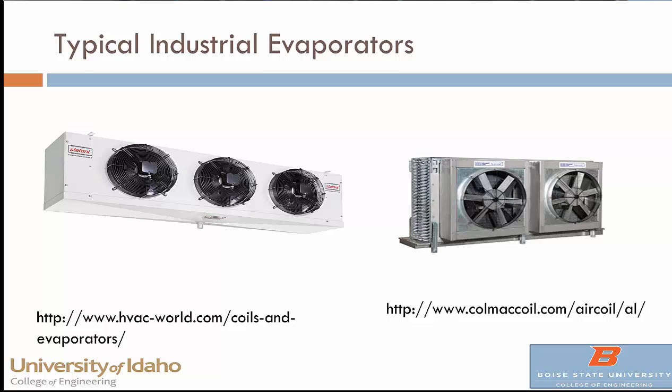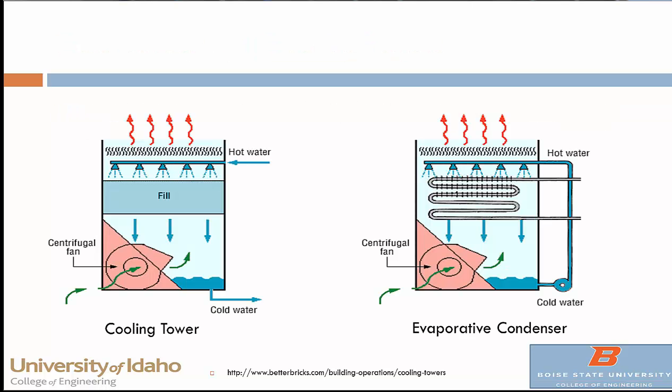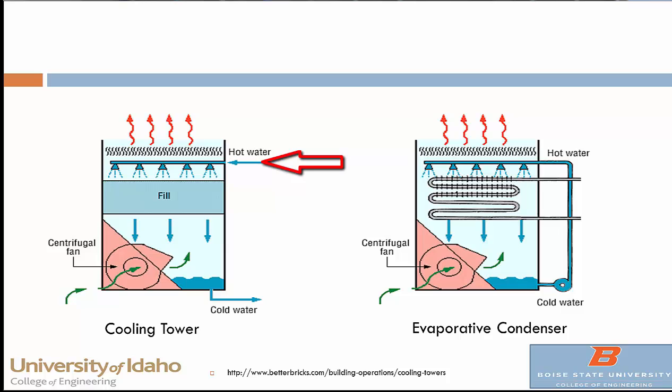In large freezer warehouses, evaporator units are mounted up high, drawing in the warmer air that has risen to the top and cooling it so it drops back down. On the other end, condensers reject heat — usually on the roof. The two most common types are the evaporative condenser and the cooling tower, which look very similar. In the evaporative condenser, water is sprayed on fins and a fan blows air against it so water evaporates and takes heat away from the refrigerant running through the condenser coil. In a cooling tower, water from the chiller runs through a medium with air blown against it, and the collected water returns to the chiller.